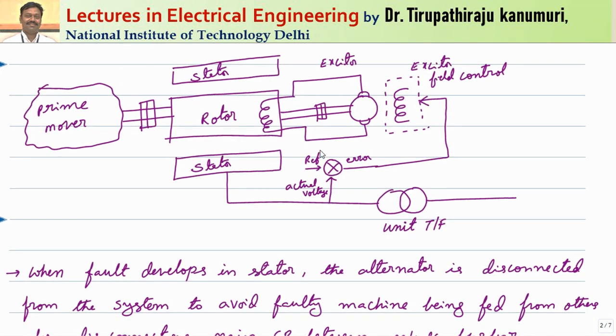If you take this system in detail, there will be a prime mover coupled to the rotor of the alternator, and also coupled to the exciter. The rotor has a field produced by the exciter. The exciter has its own field, and by controlling the field given to the exciter, it produces the DC voltage supplied to the field winding of the alternator. The actual terminal voltage is measured, compared with a reference voltage, and that error controls the exciter field. Because of this field and the rotating prime mover, EMF is induced in the stator, and the stator voltage is connected through a transformer to the grid.